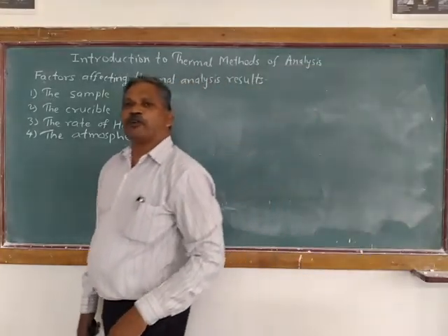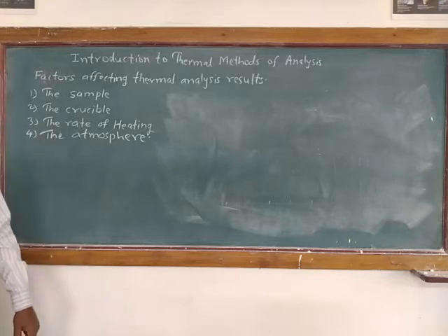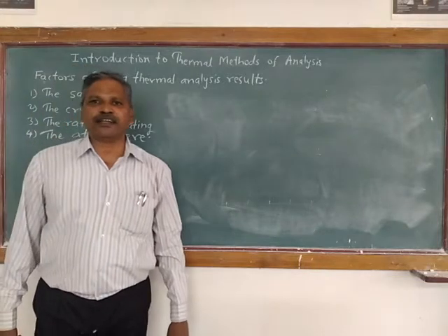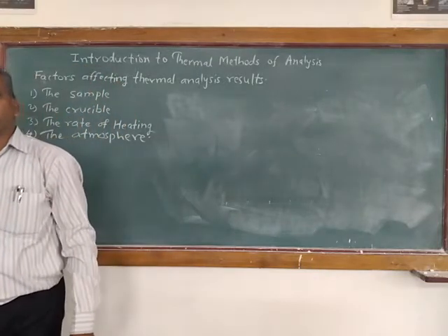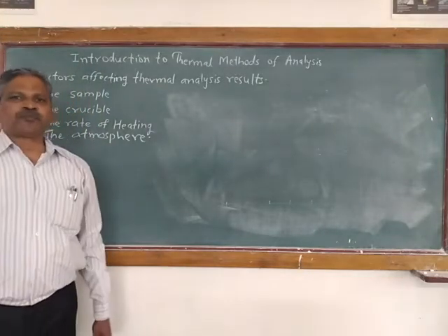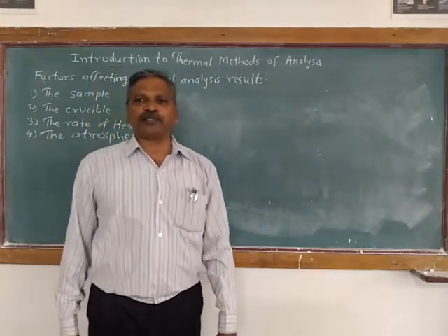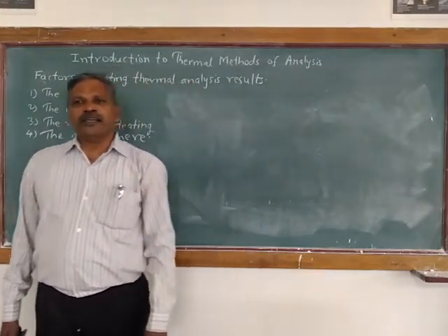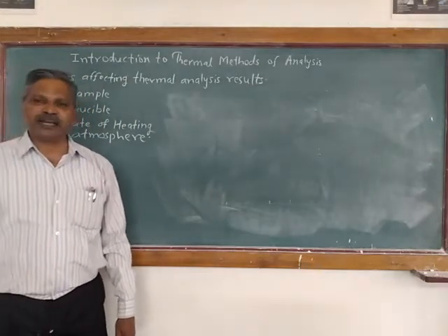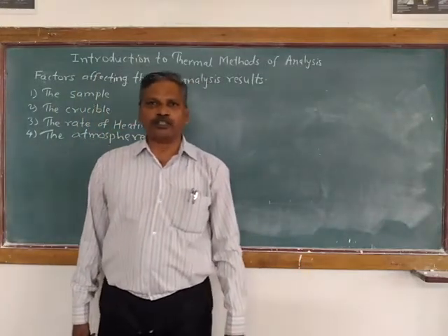Sometimes the sample produces its own generated atmosphere. This can affect the equilibrium, the kinetics and the heat transfer of the experiment. We should also consider the flow rate of the gas. A static atmosphere will not sweep away the reaction product from the sample, or it acts as a heat transfer agent. But in the case of a dynamic atmosphere, the evolved gases get swept away from the reaction product.